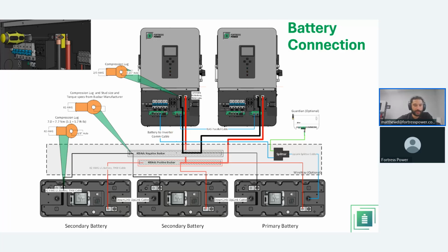The battery connection. Okay, this is a high-level overview of how your battery connection would be. Now, we would go into a typical battery to bus bar to inverter connection. There are some inverters, like the MV inverter from Fortress Power, that has the do not share battery function, but that is not applicable with the Solo 6.5. Solo 6.5, each inverter has to land on a bus bar, and from that bus bar lands into each battery individually. And so this is coming straight from the manual, but I wanted to sort of go over the philosophy and the explanation of the overview.